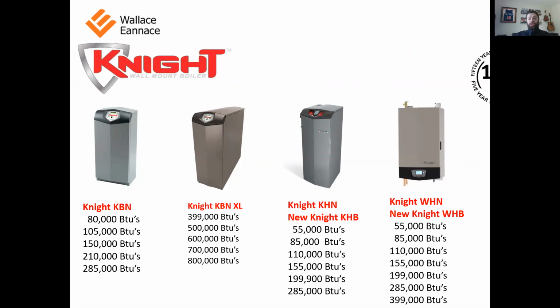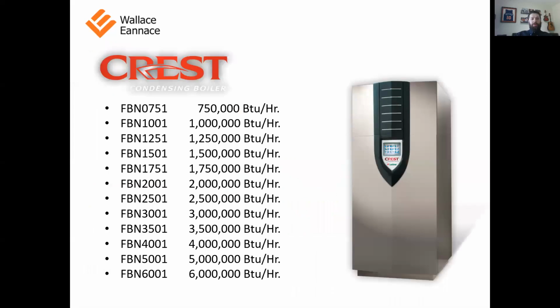These come in wall hung, starting at 55,000 BTU, up to the floor standing Knight XLs. Those go up to 800,000 BTU. So this covers a huge range, and these are good for residential, light commercial, even some bigger commercial buildings.